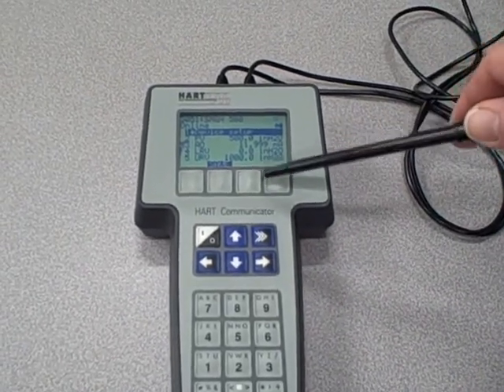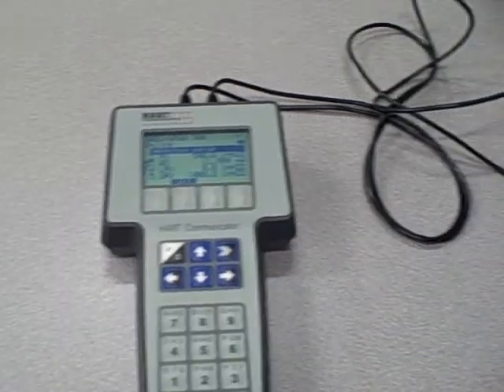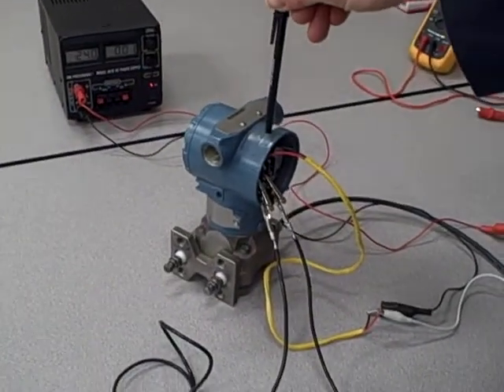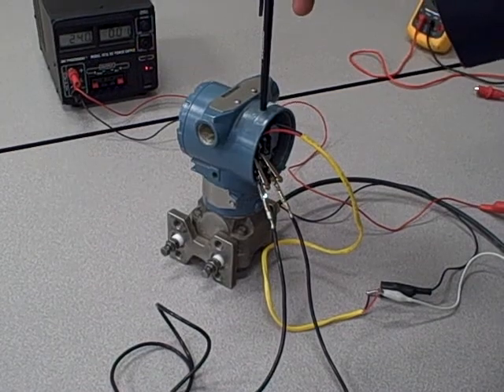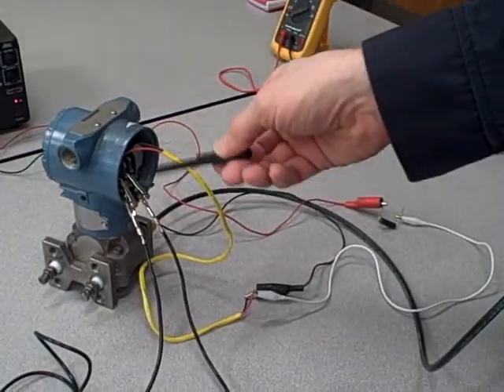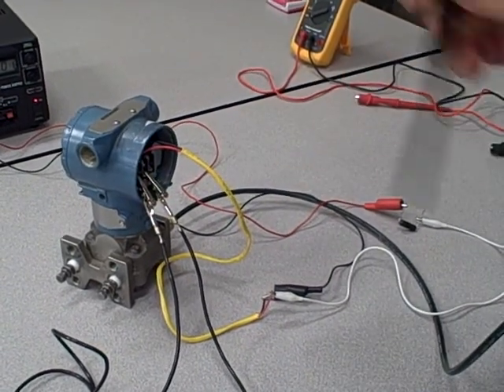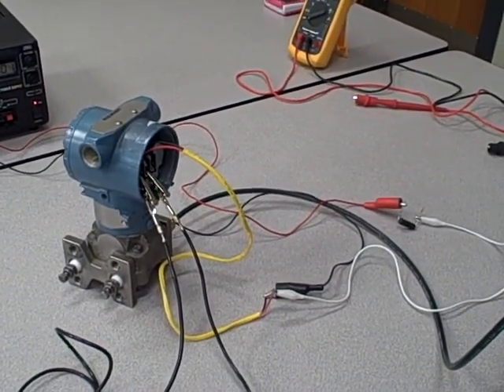Here we have a Rosemount Hart Model 275 communicator talking digitally to a Rosemount Model 3051 differential pressure transmitter. It is communicating using the Hart protocol, which is interjecting AC voltage and current signals along the same two wires that carry the 4 to 20 milliamp DC signal.